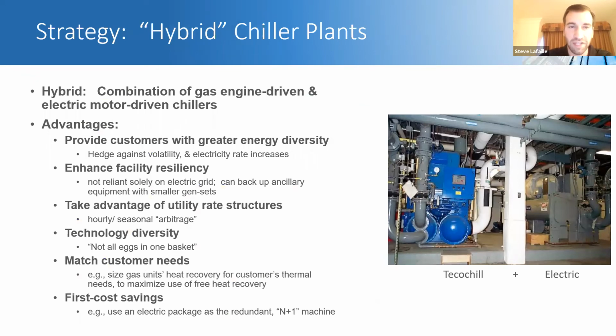So this is that concept again—a really common approach. In certain applications where there's a lot of waste heat recovery need, it does make sense to just put in all Tecochill units, and there are plenty of places like that. But normally, in maybe a hospital or a place where heat recovery needs are a little smaller, you can really get a lot of benefit by having both. For an owner, we're not asking people to put all their eggs in one basket—they want diversity of technology and diversity of energy sources. There can be first cost savings by leveraging an electric machine for an N+1 redundant chiller, since if you're not going to run the chiller very much, its operating cost implications are moot.